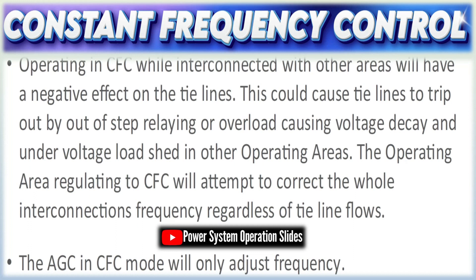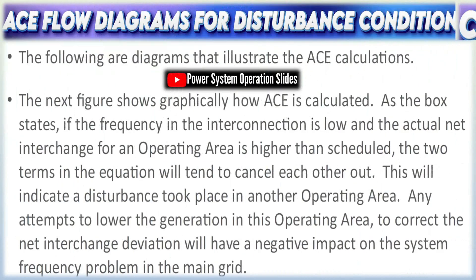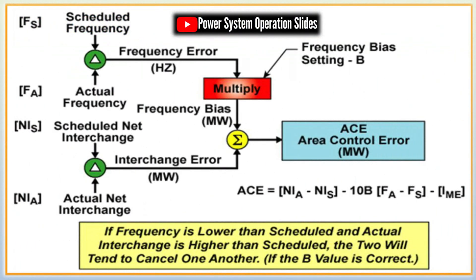The constant net interchange concept establishes that the net power exchanged over the tie lines should remain at a predetermined value. Even when local load demand changes, the interchange is held constant by adjusting the generation accordingly. Maintaining constant net interchange is essential in interconnected systems, ensuring that power trading and contractual obligations between regions are respected. In constant frequency control mode, the primary objective is solely to regulate frequency — the AGC responds to any frequency deviation caused by an imbalance of load and generation by dispatching appropriate control adjustments, thereby keeping the grid frequency near its target (e.g., 50 or 60 Hz). This is crucial since most grid-connected equipment is designed to operate within a very narrow frequency band.